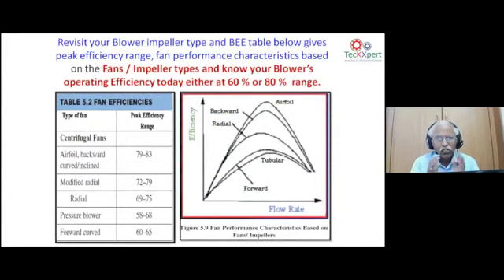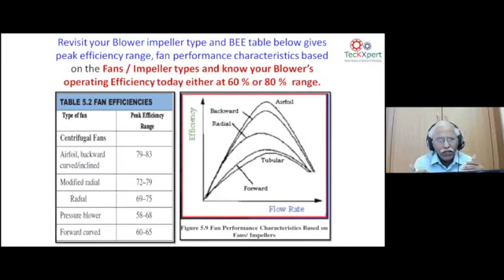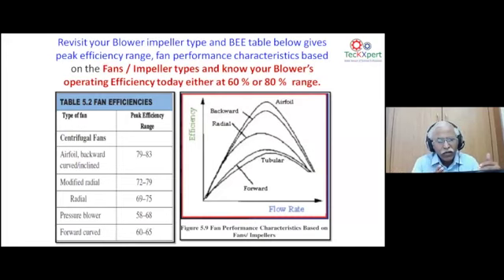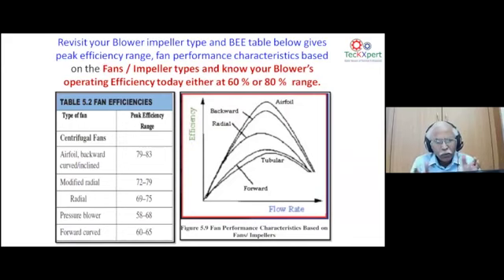Energy auditors check whether existing blowers are in line with the BEE reference table. Most industries — eight out of ten — use centrifugal backward-curved impellers. Per the reference ranges: airfoil (backward curved/inclined) achieves 79–83% efficiency; modified radial 72–79%; radial only 69–75%. Forward-curved impellers come last in efficiency. Every blower is chosen by the process expert to match process requirements, but as energy auditors we also ensure the blower efficiency is considered.